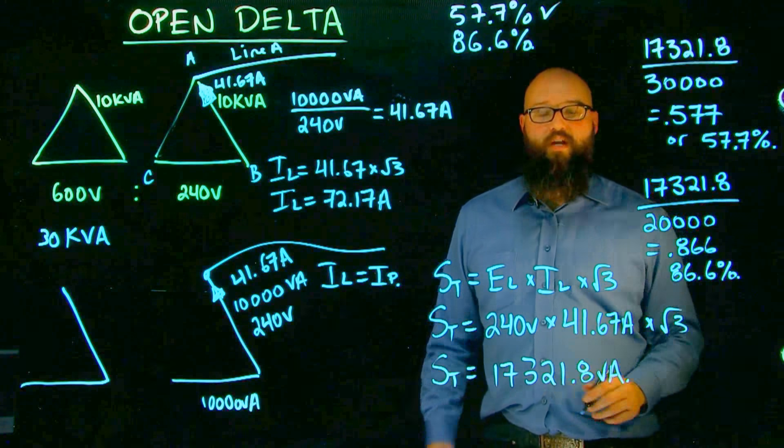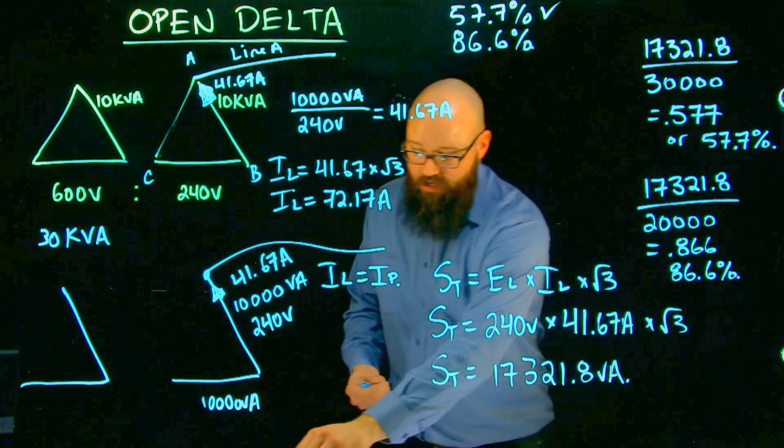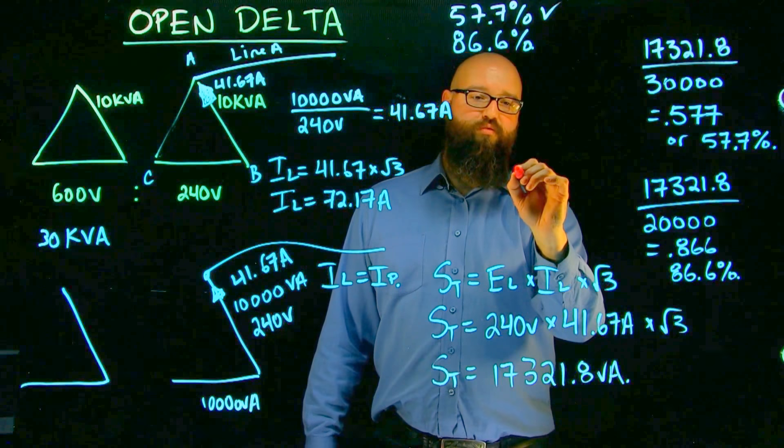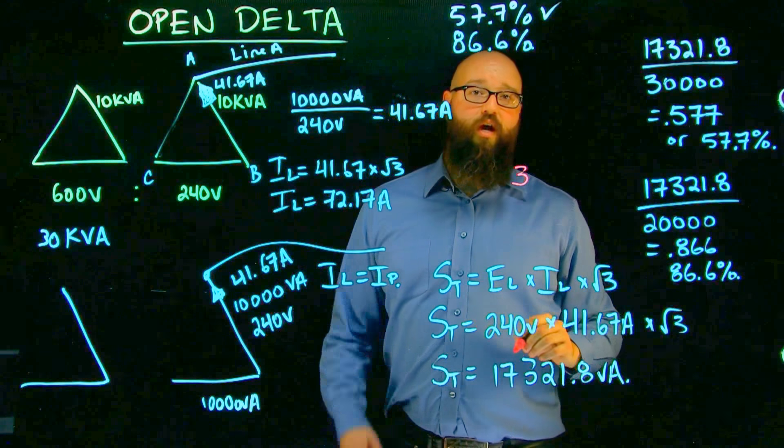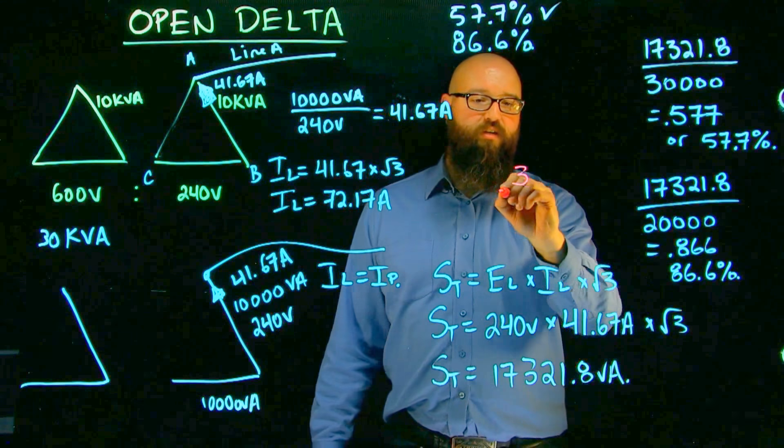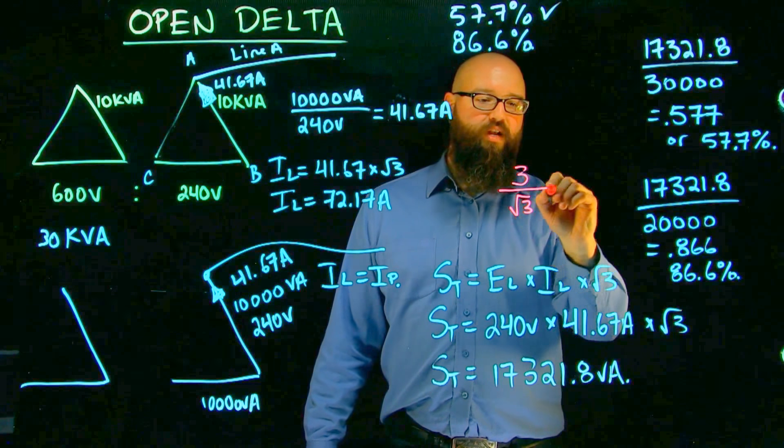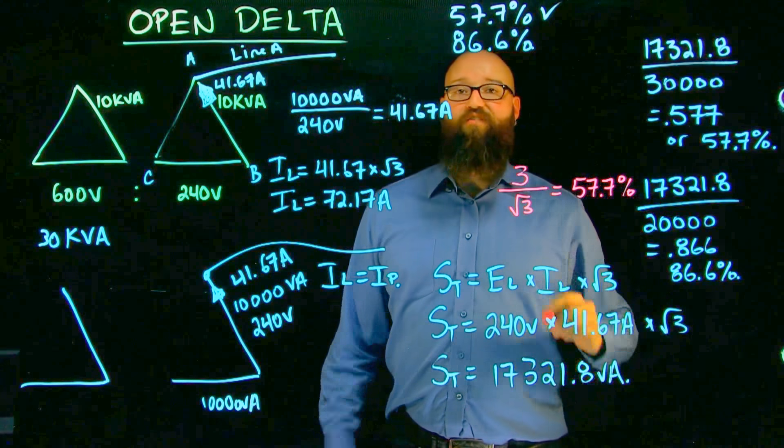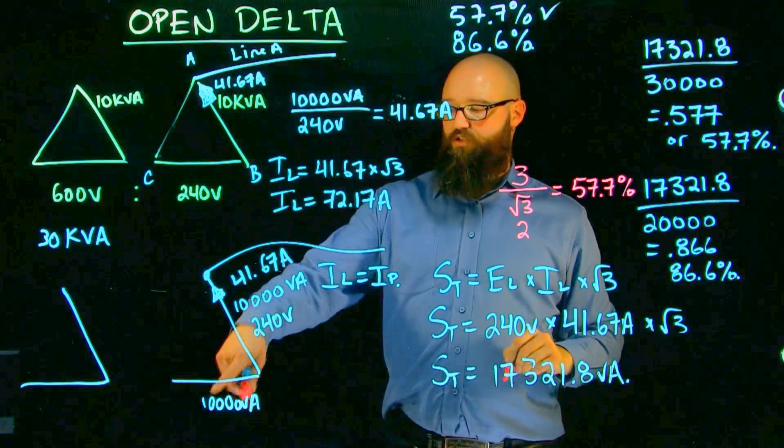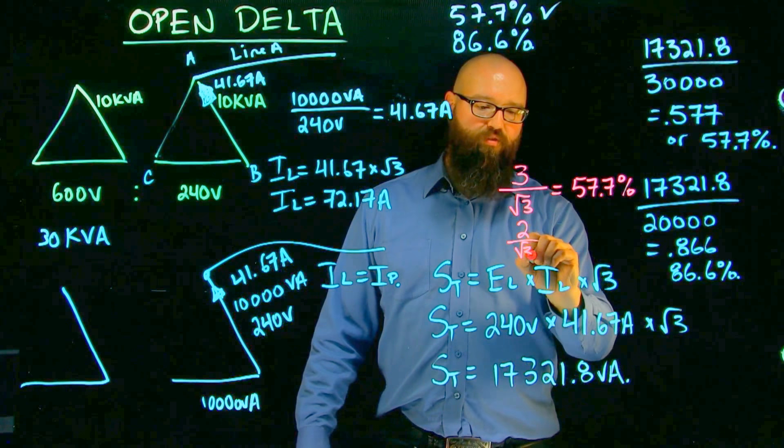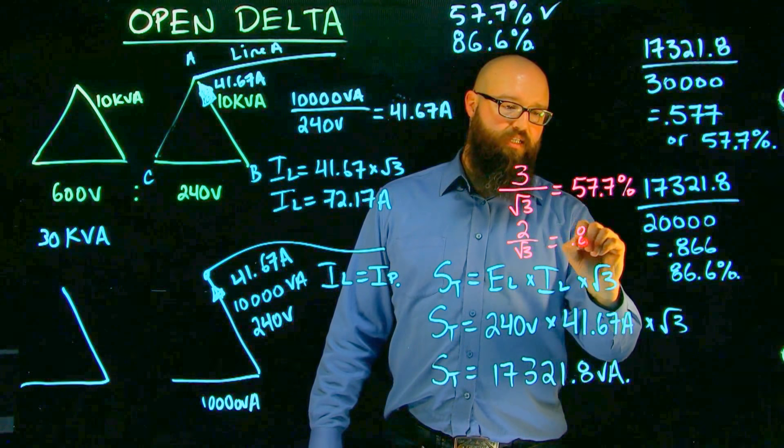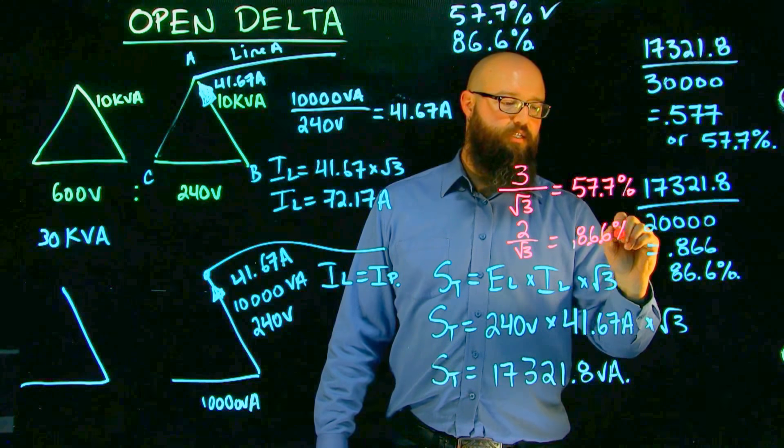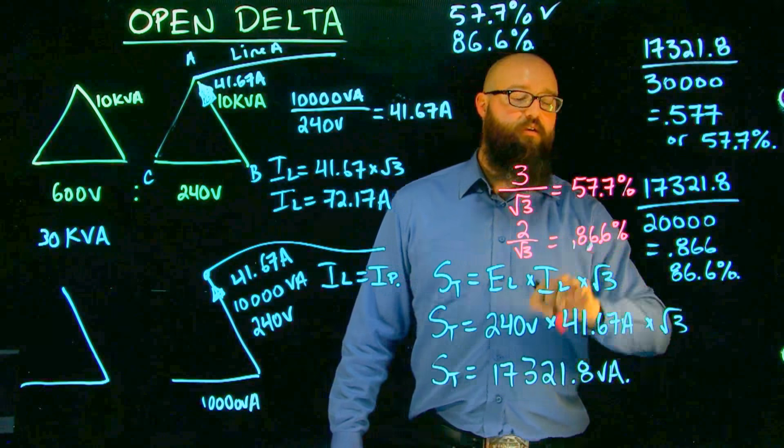Okay, another quick way to quickly calculate those out. If I have, we'll say three transformers, and I want to know what they're going to be in open delta, I can divide it by root three gives us 57.7%. And if I start with two transformer, or these two coils, and I divide it by root three, I end up with 0.866 or 86.6%. Sorry, get rid of that.